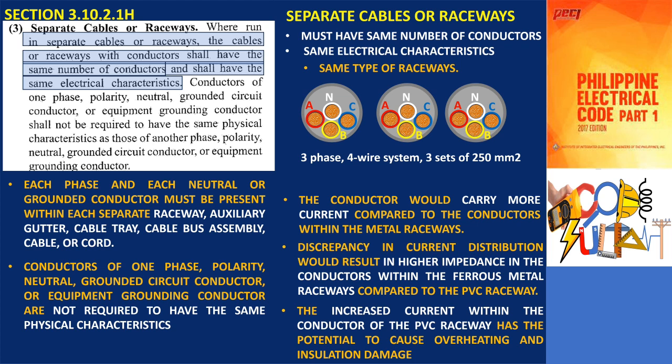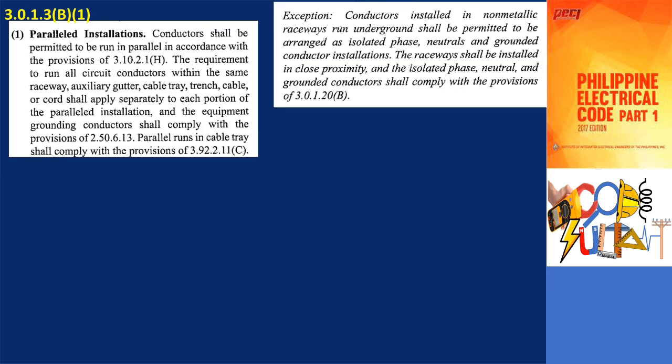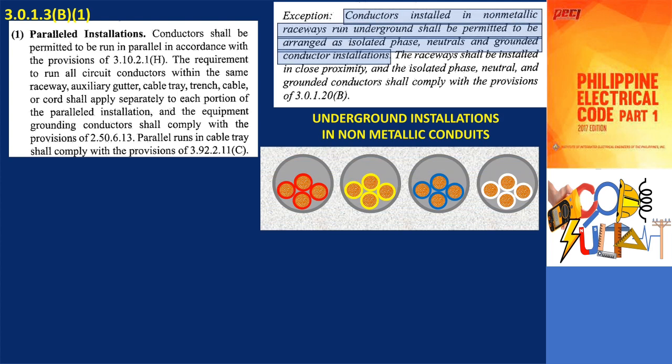Conductors of one phase, polarity, neutral, grounded circuit conductor, or equipment grounding conductor are not required to have the same physical characteristics as those of another phase, polarity, neutral, grounded circuit conductor, or equipment grounding conductor. In exception of 3.0.1.3B, one allows conductors to be installed in non-metallic raceways for underground applications.